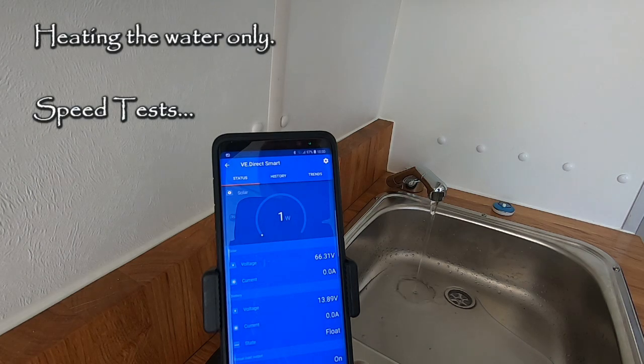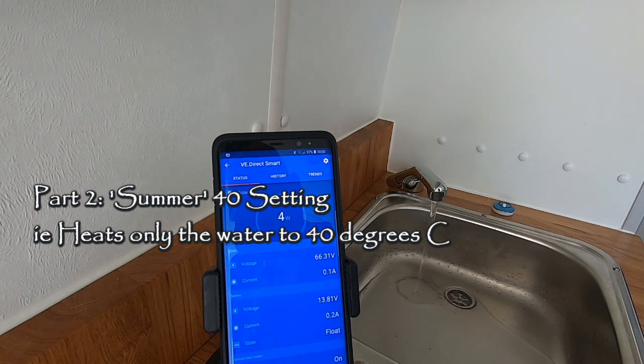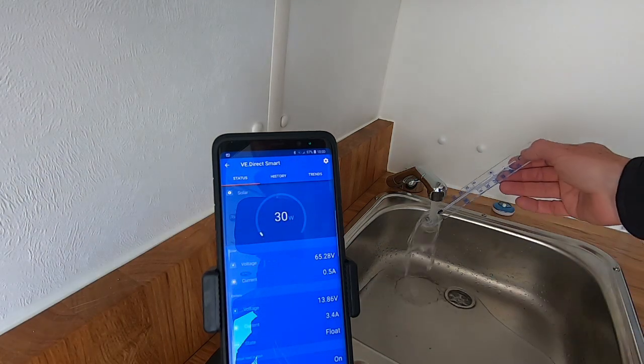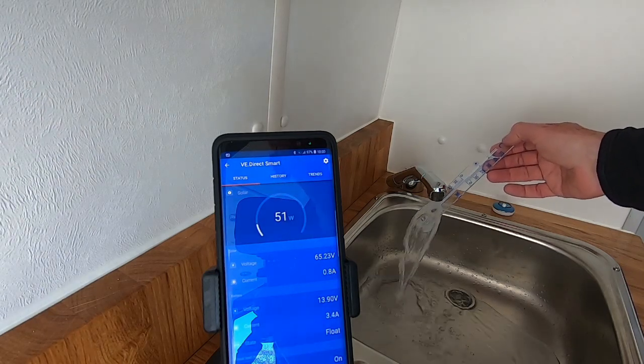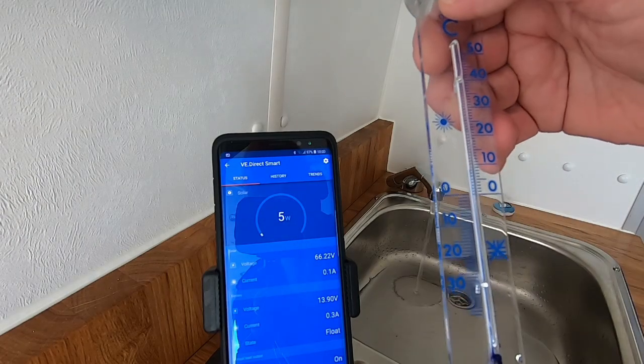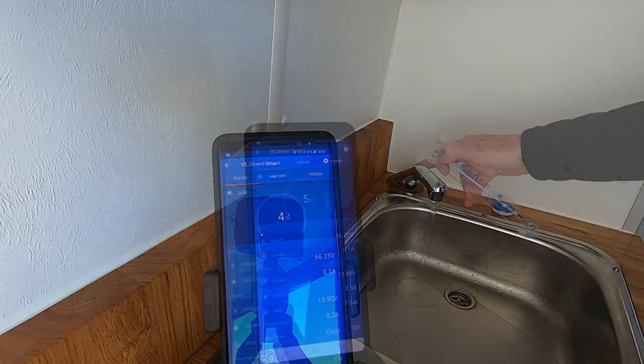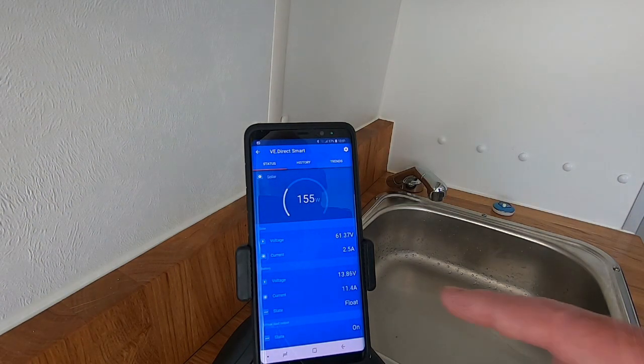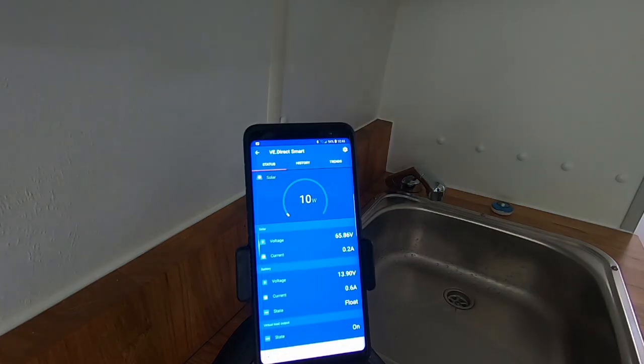This is a test of the summer setting — hot water only. I want to see how long it takes to get to 40 degrees centigrade, starting at 8 degrees. Switching on now at 10:01. After 44 minutes, the boiler has stopped and the pump has stopped.